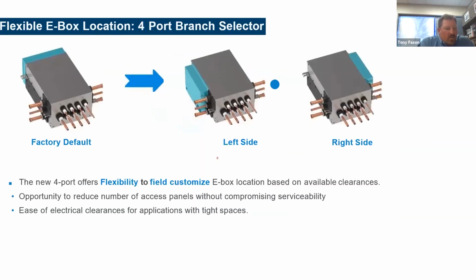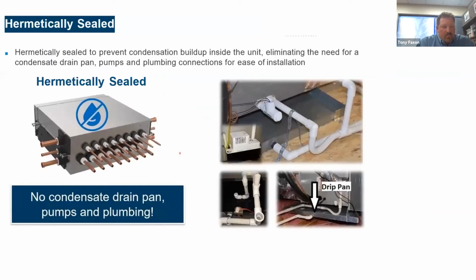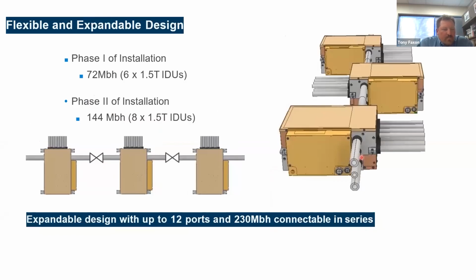Also, on the new 4-port box, which is one of the most common used, the electrical control box that you see here, which also contains the high voltage connection, obviously with US code, it's going to require 3 feet in front of it, can be moved from side to side. So it can go to left side, go to right side, and go to the back. This helps with installation and code clearances. As with all Daikin branch selector boxes, these are hermetically sealed, fully insulated. So there's no internal condensation, and there's no drain piping system required to be installed by the contractor, no secondary drain pan, all of that. Unfortunately, other manufacturers still require that drain system. Another benefit is that these boxes allow for an expandable design. The system can be installed in phases and then expanded.